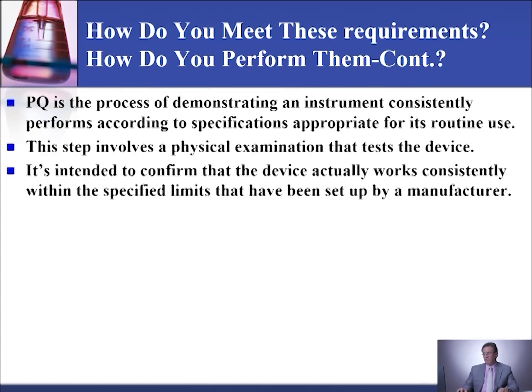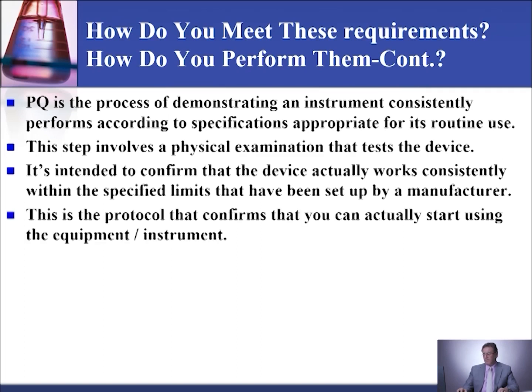Performance qualification could also be defined as the process of demonstrating that an instrument consistently performs according to specification appropriate for its routine use. This step involves a physical examination that tests the device. It's intended to confirm that the device actually works consistently within the specified limits that have been set up by the manufacturer. This is the protocol that confirms that you can actually start using the equipment or the instrument.